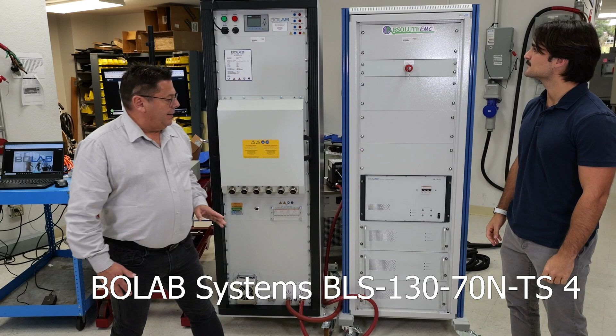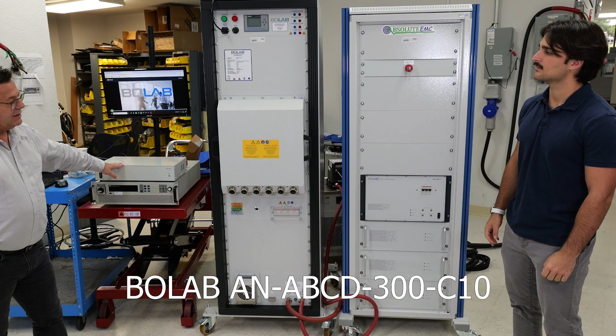The main purpose of this test system is to do inverter testing, DC-DC converter testing, and onboard charger testing according to ripple tests, load dump tests, and all these kinds of tests out of these standards. The main components required are, first of all, a 4-quadrant amplifier system, then the artificial network, and a high voltage power supply. Inside of the artificial network there is a built-in capacitor bank, as this kind of testing requires a capacitor bank of 10 millifarad, and this is all built in here.